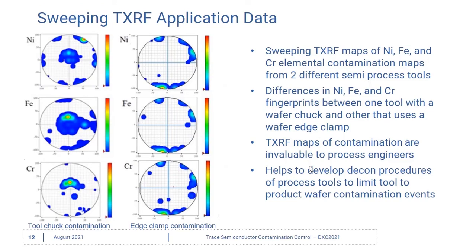Here are two examples of sweeping TXRF application data from two separate wafers, both showing nickel, iron, and chromium contamination. On this first wafer, from the first processing tool, most of the contamination for nickel, iron, and chromium came from the center of the wafer. This was determined to be coming from the tool chuck.